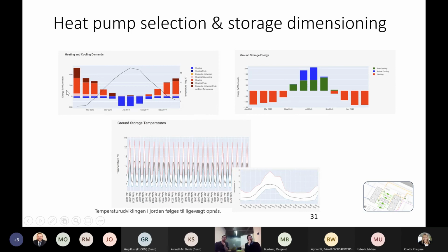To select the heat pump, we run simulations against these demands. Here we run a simulation where you can still see some peak demands for heating, provided in red by the heat pump, and also some with the subcooling circuit I briefly mentioned before, which provides all the cooling here.